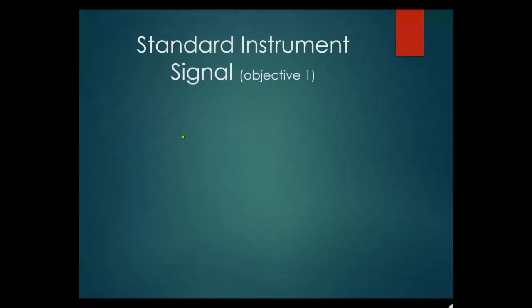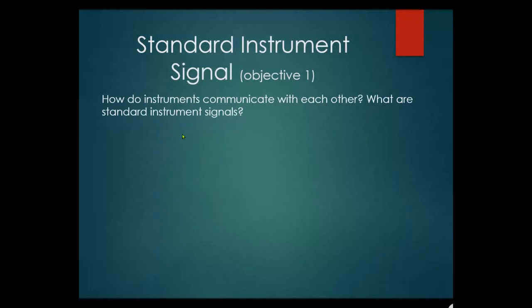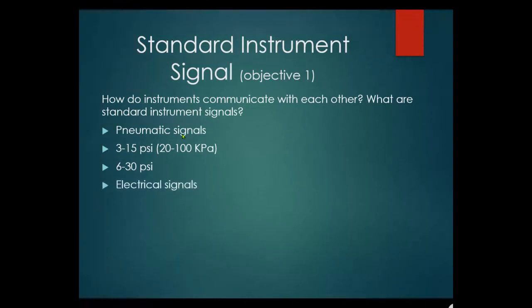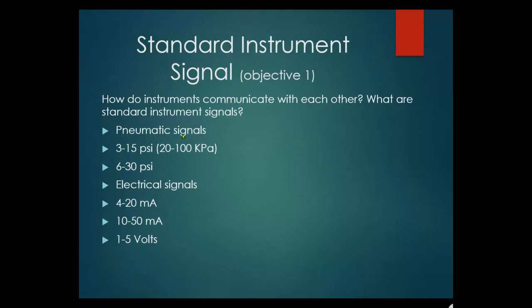Standard instrument signal transmission — how do instruments communicate with each other? The standard pneumatic signals are 3 to 15 psi or 20 to 100 kPa, most still use 3 to 15 psi. There's also 6 to 30 psi, which isn't seen much. The electrical signals are 4 to 20 milliamps, and also 10 to 50 milliamps (rarely seen), and 1 to 5 volts, which comes from your 250 ohm resistor.